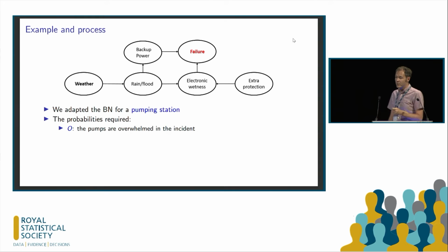So the main failure mode here was that essentially the river that the water pumping station was next to was so high that the pumps within the pumping station couldn't pump out the water fast enough, and water came in through the wet well of the pumping station and essentially came in from the inside. So it didn't come out over the barriers from the outside of the pumping station. It came up from within because it can't pump into the river quickly enough, and the rate of water coming in is faster than the rate of water coming out.